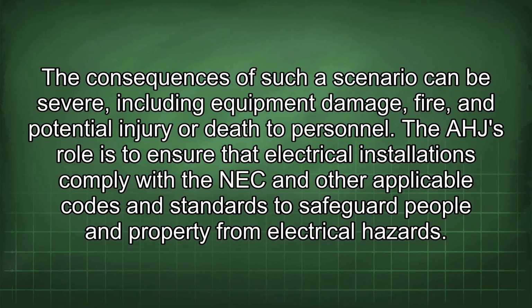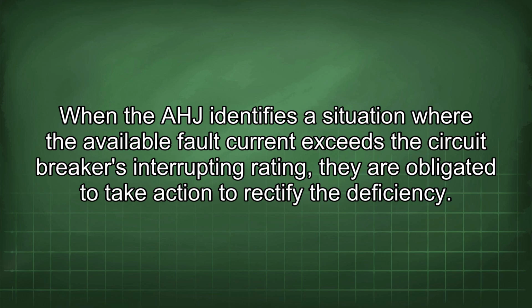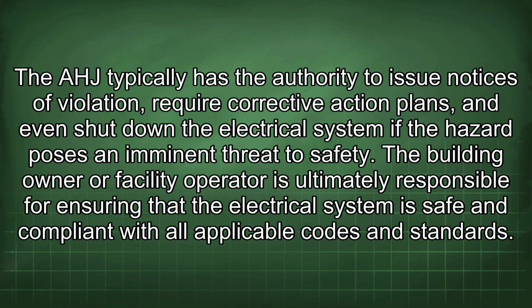The AHJ's role is to ensure that electrical installations comply with the NEC and other applicable codes and standards to safeguard people and property from electrical hazards. When the AHJ identifies a situation where the available fault current exceeds the circuit breaker's interrupting rating, they are obligated to take action to rectify the deficiency. The AHJ typically has the authority to issue notices of violation, require corrective action plans, and even shut down the electrical system if the hazard poses an imminent threat to safety.